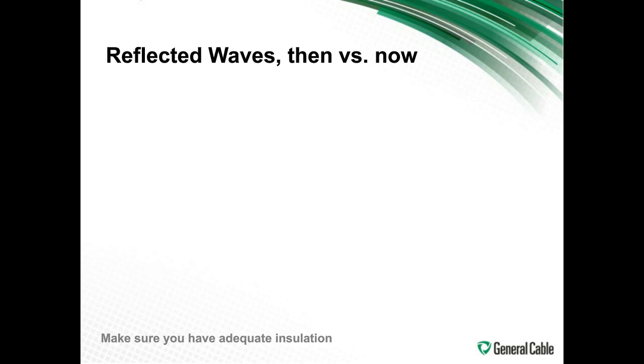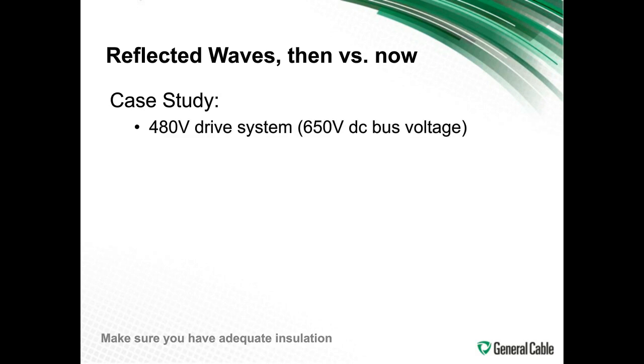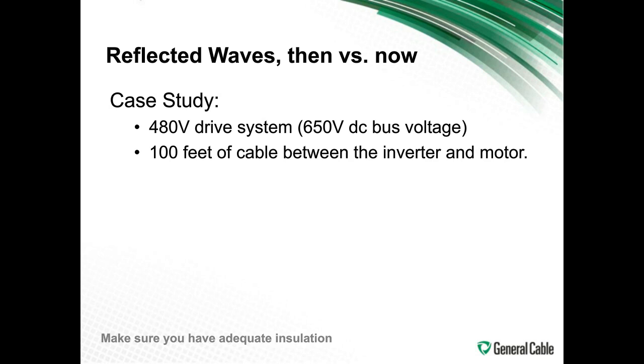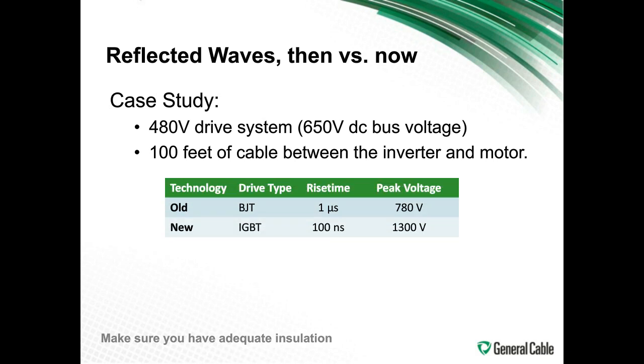So if you look at reflected waves, let's first look at a case study of a 480 volt drive system using a 650 volt DC bus voltage, and you use 100 feet of cable between the inverter and the motor. So keep that cable distance the same. Using an older drive type with the BJT technology, rise time is 1 microsecond, and the peak voltage is 780 volts. With the newer technology, the rise time is 100 nanoseconds, and the peak voltage is 1300 volts. Cables can see twice the drive voltage.